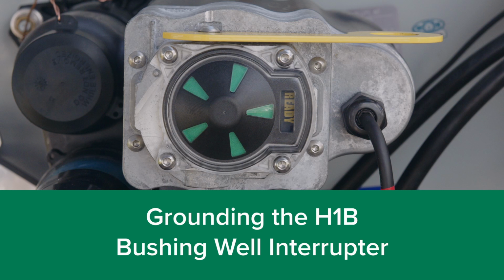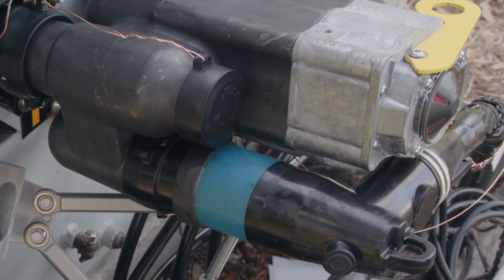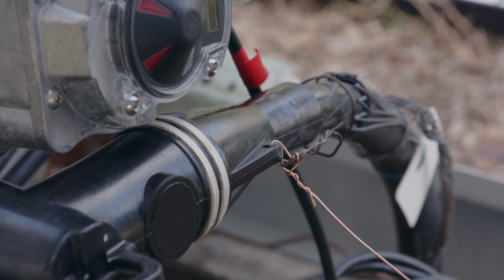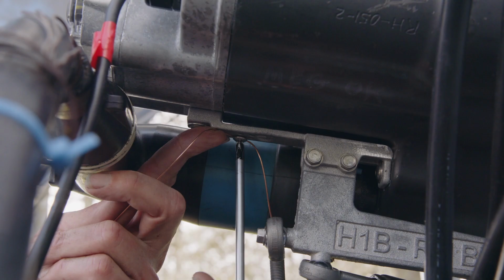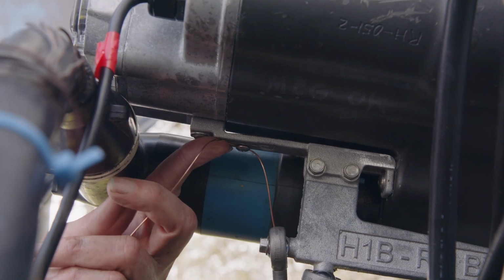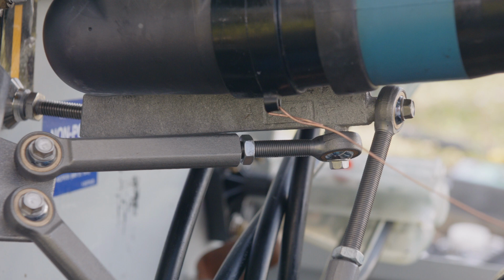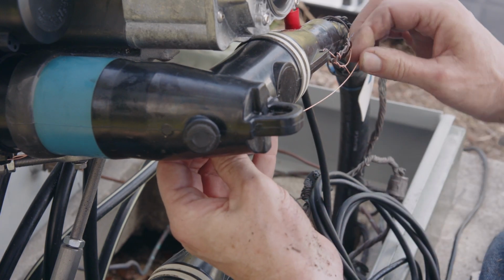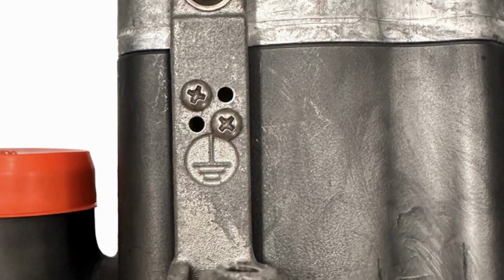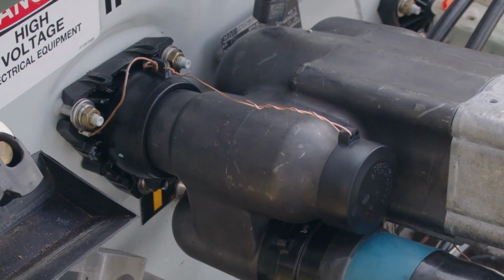Grounding the H1B bushing well interrupter. Step 1. Install the load break insert and connecting cable according to standard utility practice. Step 2. Connect the drain wire from the tab on the load break insert to the grounding point on the bushing well interrupter and continue on to the elbow neutral. Leave enough slack in the drain wire to enable parking if desired. The grounding point is marked with the symbol for earth ground and 2 holes are provided for attaching drain wires. Be sure to ground the H1B bushing well interrupter cap as shown here.